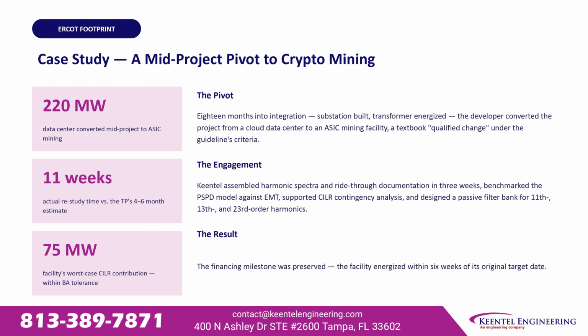Our second case study, a 220-megawatt facility approved as a data center in the ERCOT footprint. 18 months into construction, with the substation built and the transformer energized, the developer pivoted to an ASIC crypto mining facility, a textbook-qualified change. We assembled harmonic spectra and ride-through documentation in 3 weeks, benchmarked the dynamic model against an electromagnetic transient model, supported the load reduction contingency analysis, and designed a passive filter bank for the affected harmonic orders. The restudy closed in 11 weeks against the transmission planner's 4 to 6 month estimate.